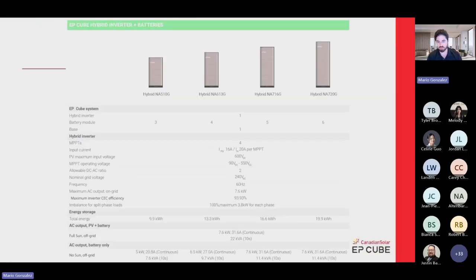I just wanted to make sure that you guys understand the capacity of each battery. Our inverter is 7.6, yes, but with no sun, that's the backup capability of the unit, because if you had an outage at night, you don't have the sun to back you up. So you want to size your projects, or your houses or systems, however you want to call it, based on this continuous output, right?